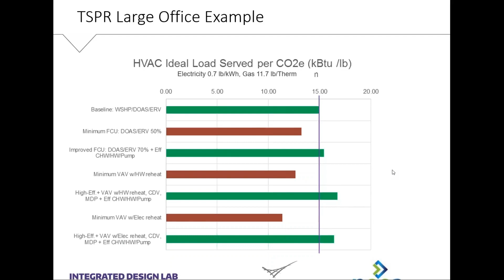This is just a sample output report. Through the click-through demo, we'll actually create a building and walk through a detailed sample report. At a high level, the report has a lot of information. Of course, it provides the proposed and baseline building TSPR, and it also identifies, based on these results, whether the building complies with the Washington State Energy Code. It has 4 other sections. The first section identifies the whole building HVAC site energy use by end use, the heating and cooling loads. Here, this information is given for the proposed and baseline building, and you can compare and see which end use is efficient, which is not, and you can think about improving the mechanical system accordingly if it doesn't comply with TSPR requirements.